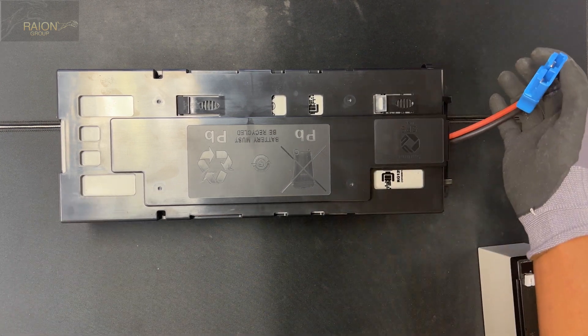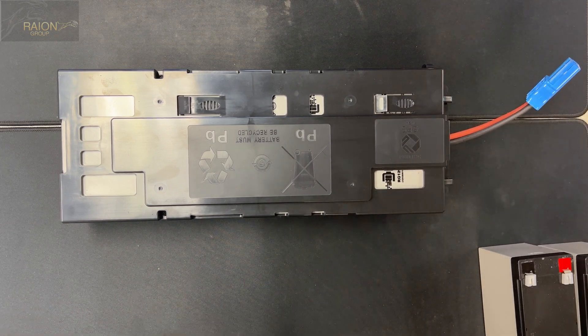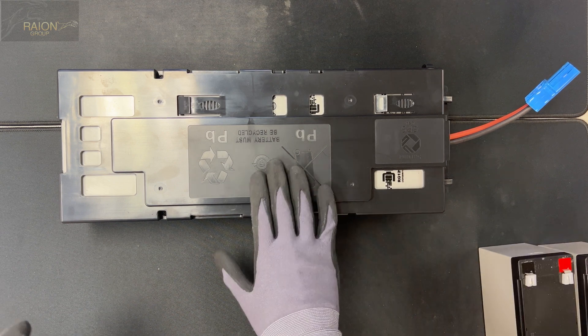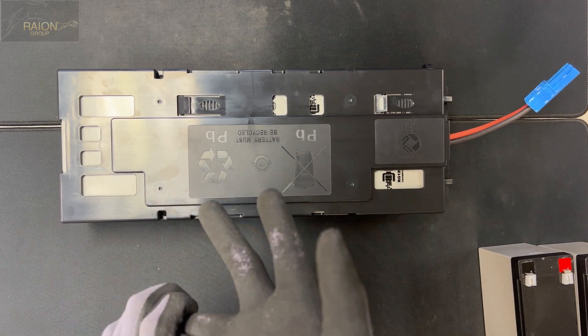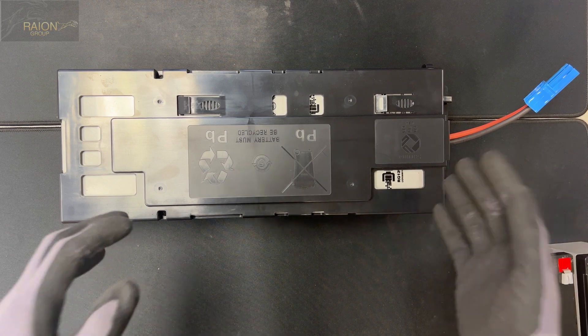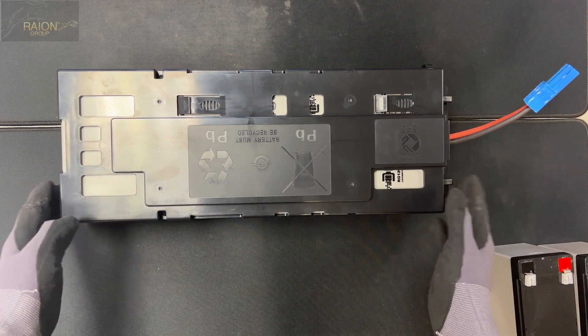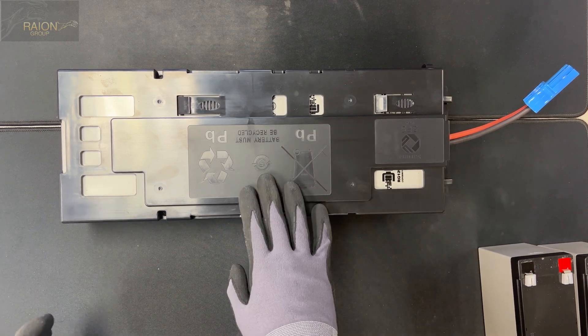So we check the polarity and as an added benefit, we have a room full of racks of UPS connected into the wall and we install these into those UPS units. We make sure it's load tested and charged within the UPS unit it's designed to go into before we approve the quality control of each unit and before we ship these out to you.